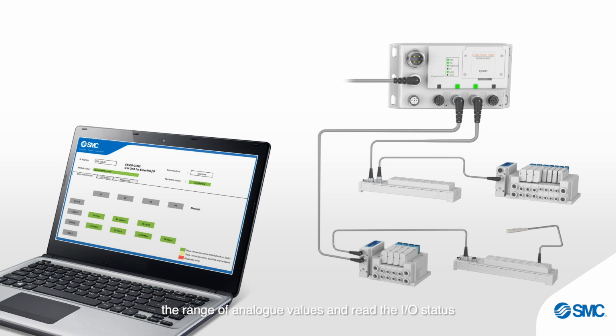Users can also read common drive alarms, such as overload. Concerning fieldbus systems, the most important parameter data to set are the range of analog values and read the I/O status, along with an ability to force the operation of valves without the use of a PLC. This can be useful, for example, in the pre-commissioning phase.